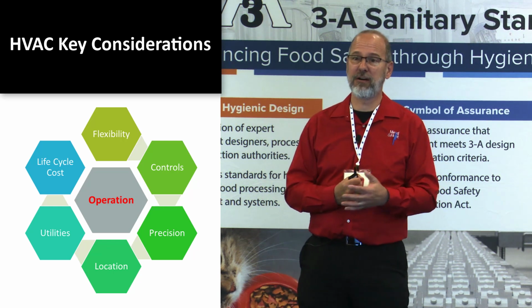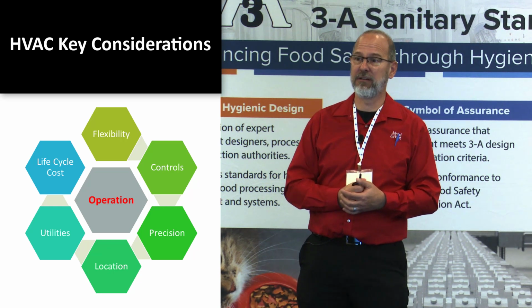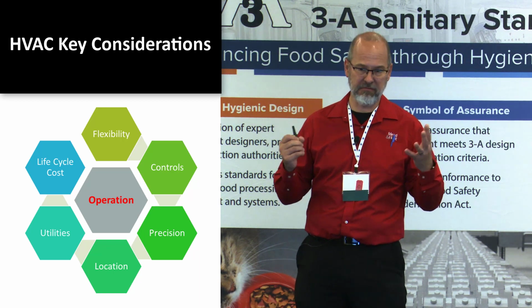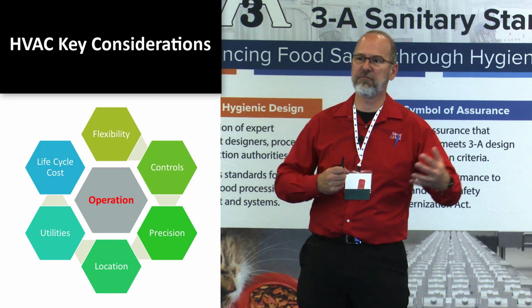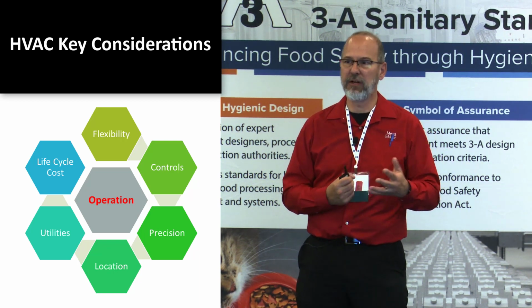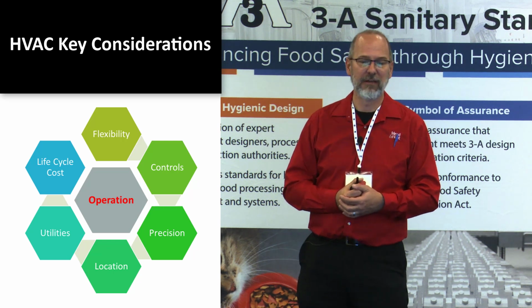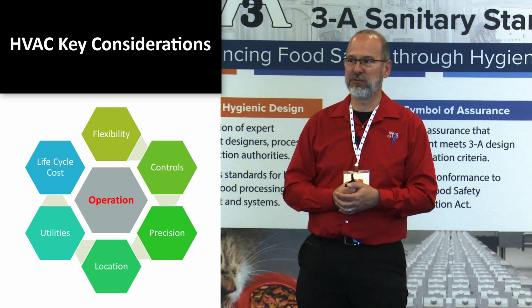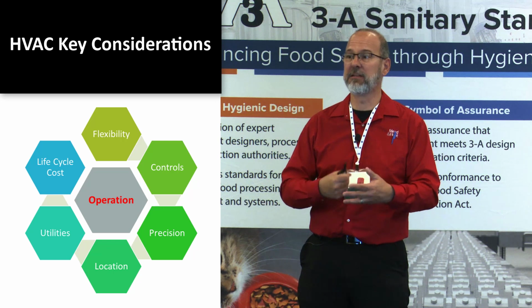Location, where are you going to put it? These units are very large. They're a lot bigger than a commercial grade air handler. So it's not uncommon for them to be upwards of 40 feet long, 12 feet wide, 10 feet high, and weigh 20, 30,000 pounds. So making sure you've got space to put these units in and to access them and get in them and clean them is important.